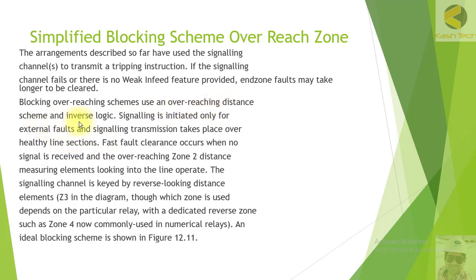The blocking overreaching scheme uses an overreaching distance scheme with inverse logic — signaling is initiated only for external faults, and signaling transmission takes place accordingly. For healthy line sections, fast fault clearance occurs when no signal is received and the overreaching zone 2 distance measuring elements looking into the line operate. The signaling channel is keyed by a reverse-looking distance element, typically zone 3, depending on the particular relay.